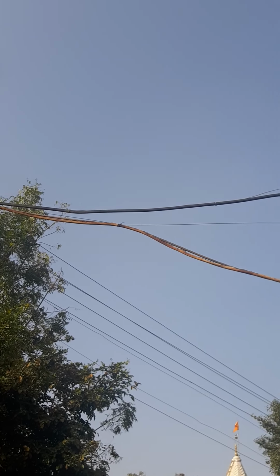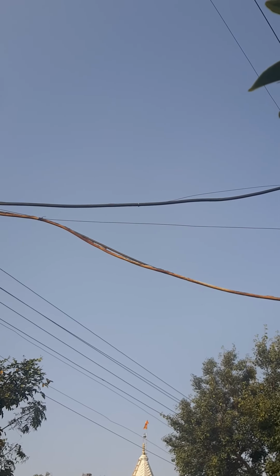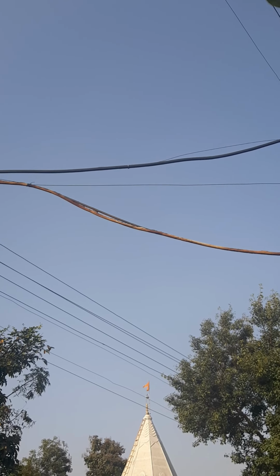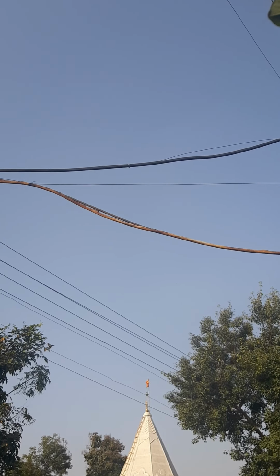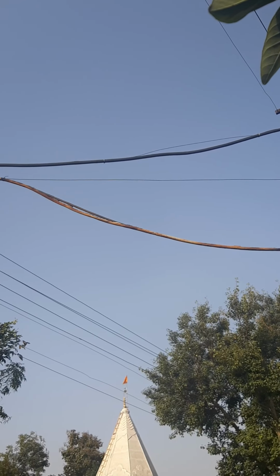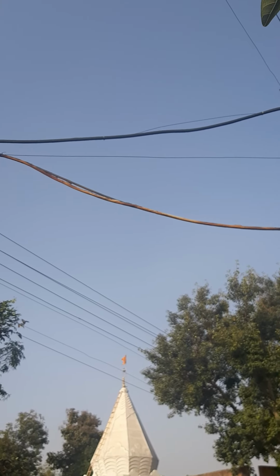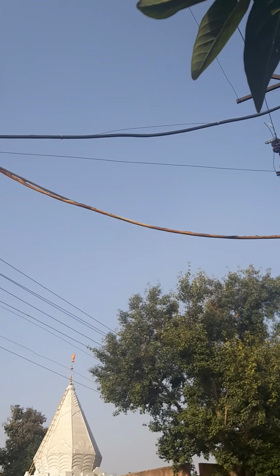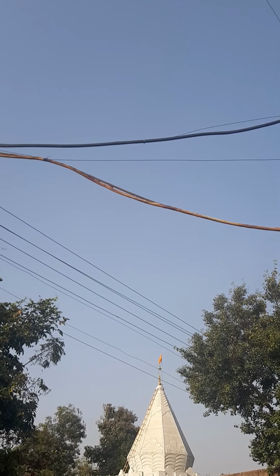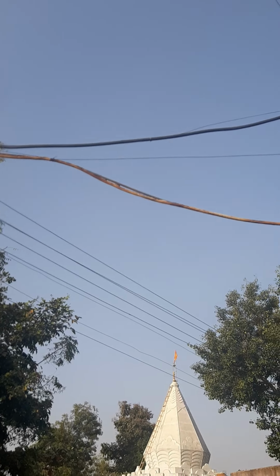This is a very defective way, and here the insulation has to perform two duties: to give insulation to the cable and perform mechanical support to the cable. That is, insulation has to perform two functions, mechanical and electrical.